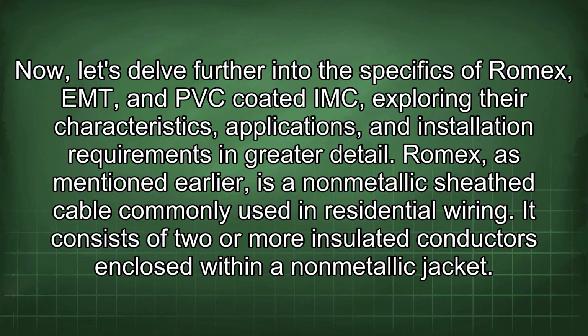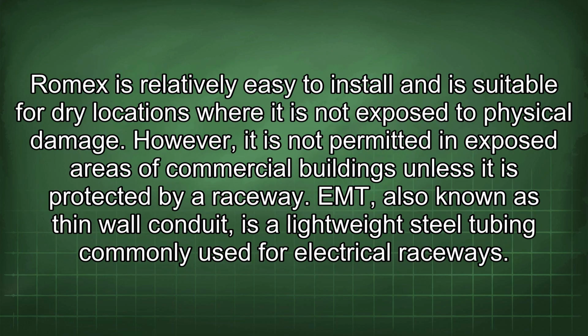It consists of two or more insulated conductors enclosed within a non-metallic jacket. Romex is relatively easy to install and is suitable for dry locations where it is not exposed to physical damage. However, it is not permitted in exposed areas of commercial buildings unless it is protected by a raceway.